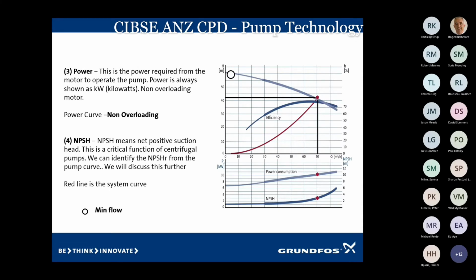Next to is the power curve, and you can see in the box just below, we now have 2 more curves, and we've got the power consumption curve, and that's relative to flow. As we increase the flow rate, we obviously increase the power. The performance curve is what we call full non-overloading. So that means the motor that is fitted to that pump will follow the complete pump performance curve, and it won't overload.